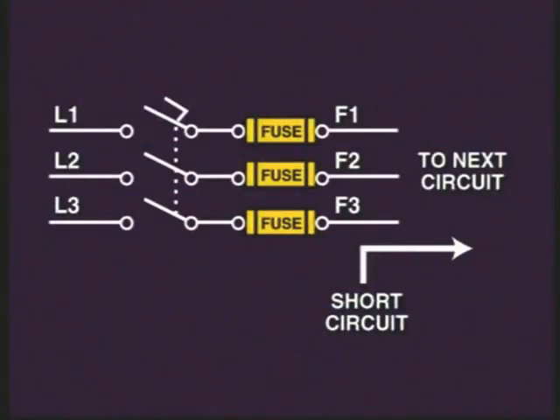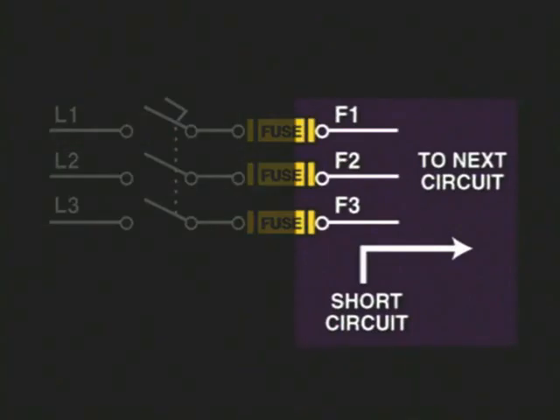If, after replacing one or more blown fuses, the system continues to blow them again, then it could be a short between the protection here and that of the next circuit. Troubleshooting a control circuit may not be as complicated and difficult as it might appear at first glance, as long as we keep our technique according to a step-by-step procedure.